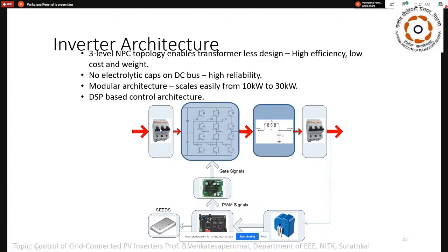This is my power architecture. You can see that the DC side, actually this breaker should not be here. The DC side breaker is altogether different. DC breakers are very, very costlier. We cannot use an AC breaker for the DC side. This picture is wrong, so you cannot use this picture for any of these things. A proper DC breaker has to be there.